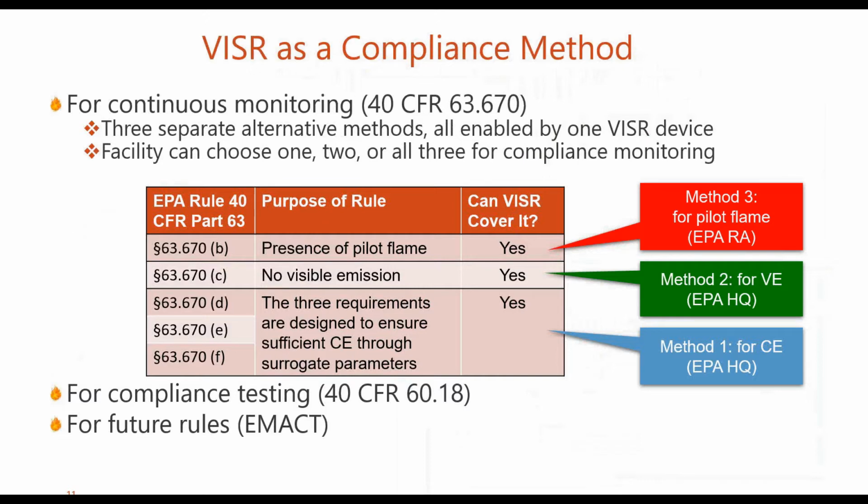You directly measure the combustion efficiency, maintain it above a 96.5% compliance point, and you're done with one instrument. Demonstrate compliance. And a significant benefit of using VISR as your compliance device is there's no latency to this instrument.